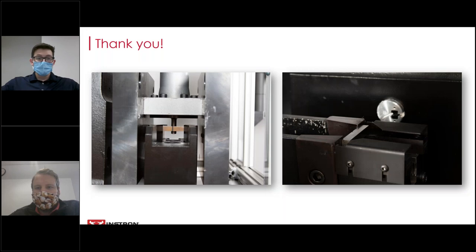Yeah, so another good question. If you remember early on, we were talking about U and C-shaped strikers. And if you can see on the left here, we have a U-shaped striker. So the reason that it can be costly is because if you remember the Izod striker, you have your specimen oriented vertically. So the C would collide with your supports if you were to test Izod with a C-shape. So that being said, you would need to swap out your whole arm and hammer, which, depending if you have service do it and to reinstall it, can certainly be costly and take some time for sure. Good question.